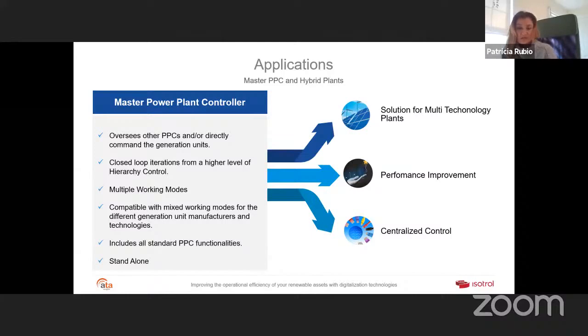For the extension, a new group of generation units by a different manufacturer was included in the project. This came with an additional PPC, which was installed with control reference, which were below the main medium voltage bus. This means that they were now contemplating a two-phase project with one previous phase, a PPC that was overseeing the new phase without accounting for it as its own. So without a master PPC, these two phases would have conflicted and fought for production and voltage control, potentially one of them weakening the other's lower phase.